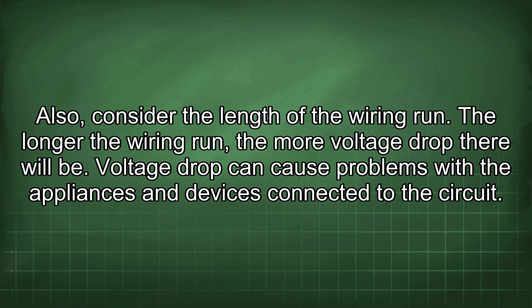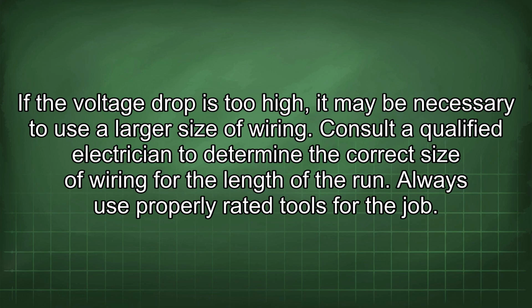Also, consider the length of the wiring run. The longer the wiring run, the more voltage drop there will be. Voltage drop can cause problems with the appliances and devices connected to the circuit. If the voltage drop is too high, it may be necessary to use a larger size of wiring. Consult a qualified electrician to determine the correct size of wiring for the length of the run.